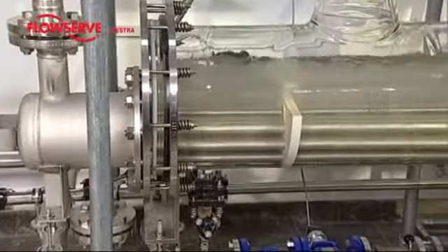The water starts to heat up. The thermal currents can be seen clearly. Cords can be seen moving through the water. At a temperature of about 60 degrees centigrade, the water is no longer able to hold the entire quantity of oxygen, and we observe small bubbles creating foam on the surface of the water. These consist of non-condensable gases which then pass into the gas phase, that is, the steam space.